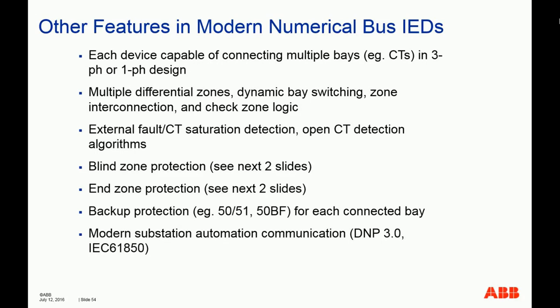And then modern numerical bus IEDs should all be equipped with these types of functions. We talked a little bit about it before. Multiple differential zones, so you can freely divide the bus differential into different zones, so they operate separately. You can assign different CTs to different zones, for example. Dynamic bus switching. The CT needs to be able to switch to which zone, depending on the status of the switch or the status of the breaker or whatever logic you create. So basically, you need to be able to dynamically switch the CT.